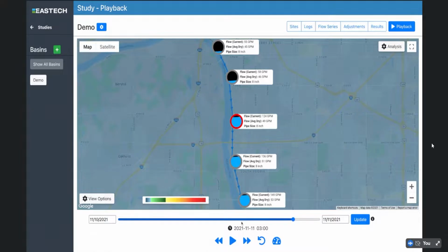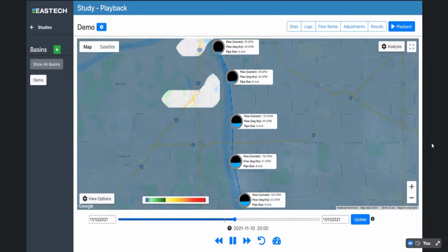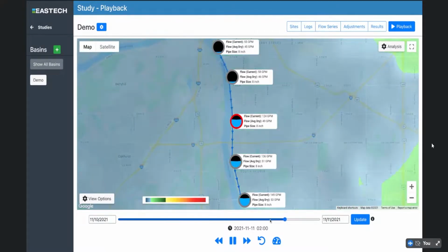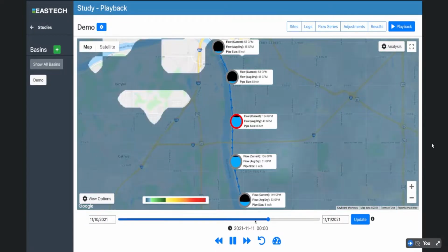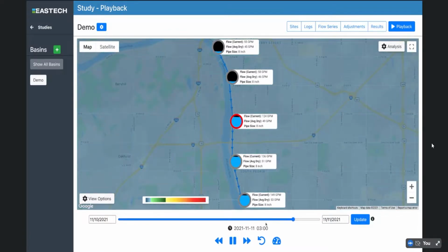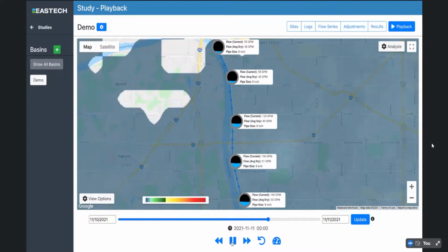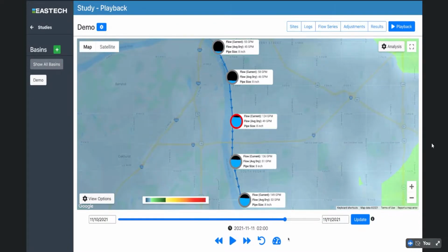Yeah, and this coupled with the auto analysis really gives you the ability to go through and not only analyze what your system normals are, not just see what existing problems I already have within the system, but to see what happens dynamically, in almost a near real-time way, looking at the weather and precipitation types that affect your sewage and wastewater collection system, and to see what happens whenever they're under duress in a fashion like this, where we see the red ring around the manhole actually come up and dynamically tell us, during this rain event, I have rain-derived I&I and potentially a surcharge condition in that particular manhole.